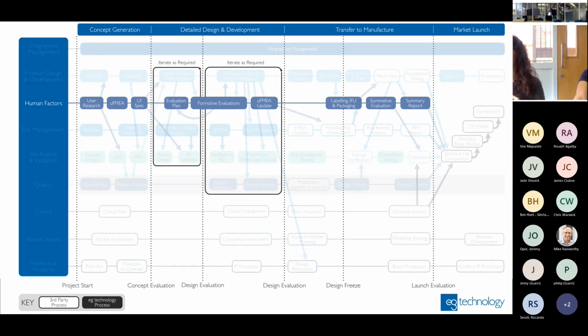So looking at human factors closely, as you see, the human factors process, the usability engineering process, starts all the way from the very beginning of your development program right through to as you compile your technical file and look to launch your product. So that's important. You can't leave it till the last minute and shoehorn it in, especially from a regulatory perspective. It does need to be thought about at the beginning and carry all the way through. And as you see, it starts with the user research stage, which overlaps with voice of the customer.